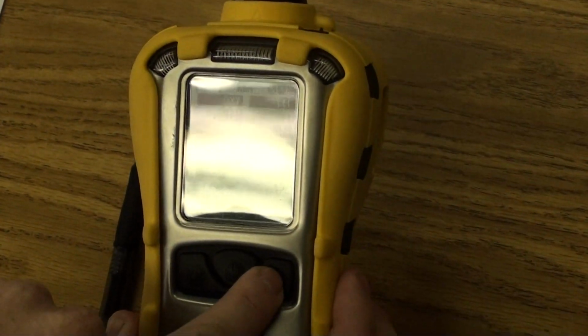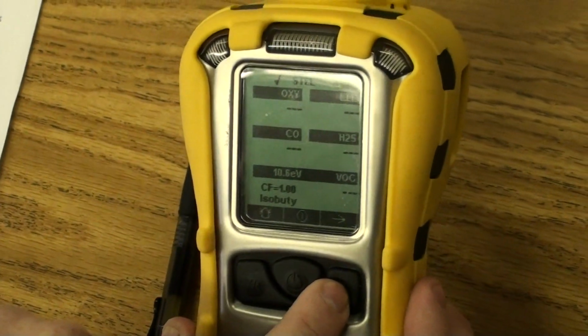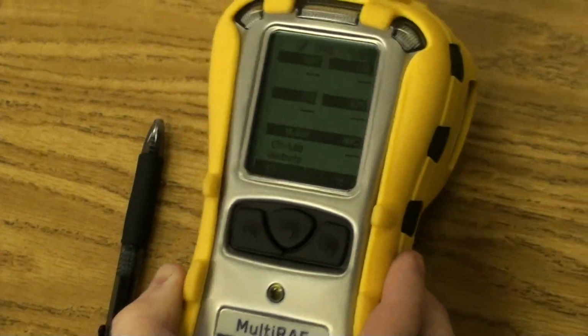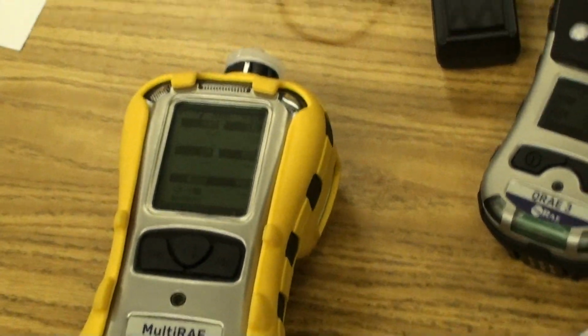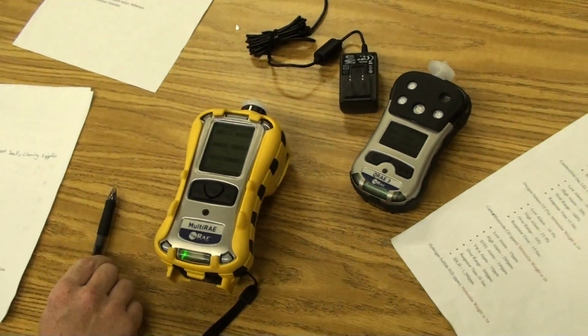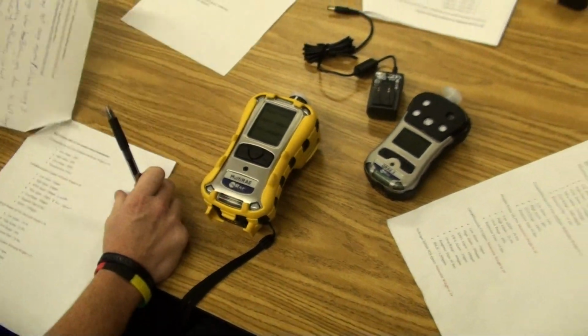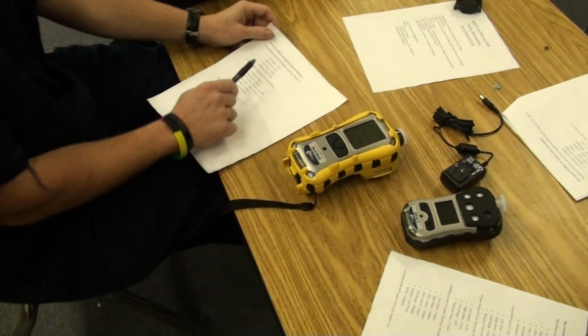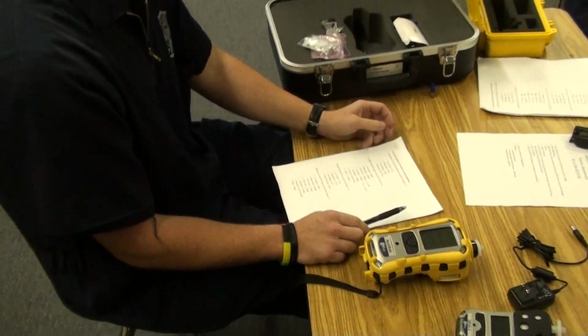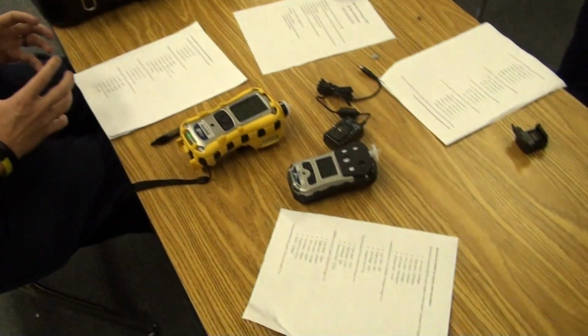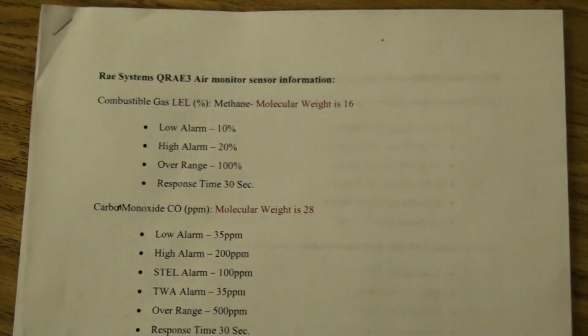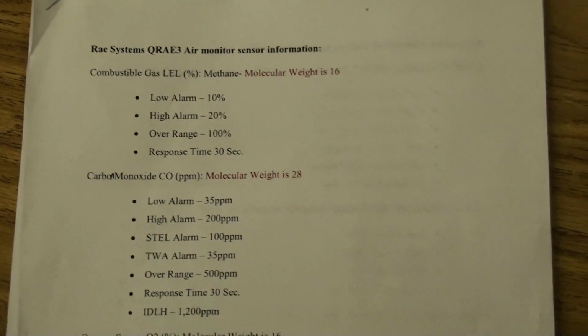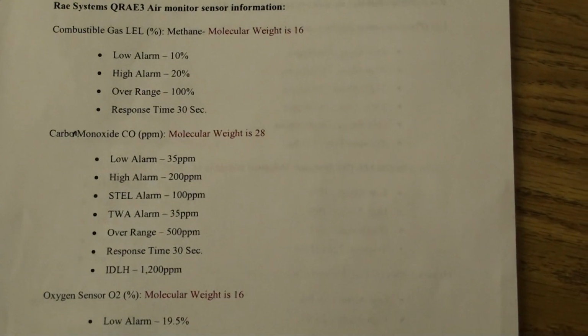They both have the whole scroll through, mins, maximums, short term, and battery percentage. It's the same on both of them. These are not, they also, on this information here, I wrote over ranges, and that's just a large amount. You don't want to get to that over range if it's percentage or parts per million, because it can supersaturate the little sensor in there, and it can ruin that sensor.